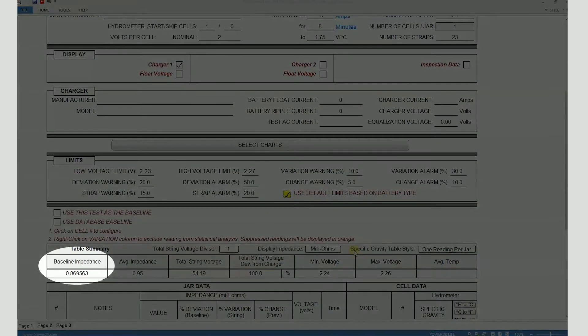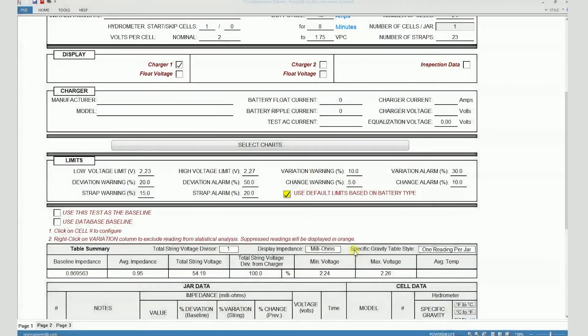Baseline impedance is kind of like the main reference value with which all the individual impedance values are compared. There are different ways of setting the baseline impedance. If you test on a battery string for the first time, then you would use those values to come up with the baseline impedance for that battery string. In that case, what you would do is check this box.